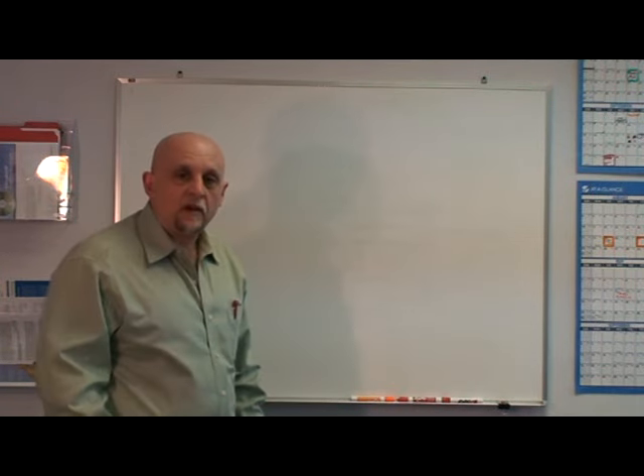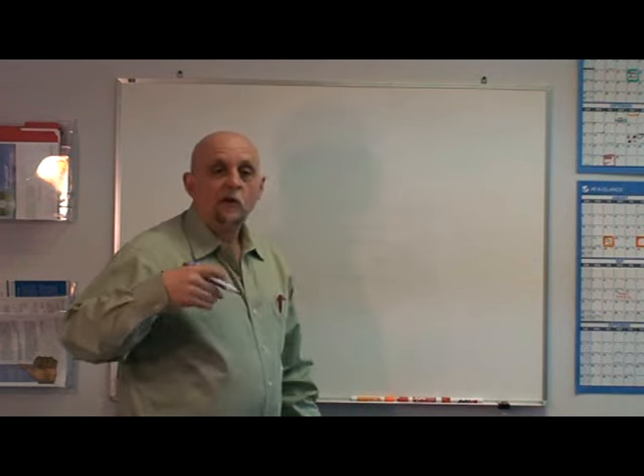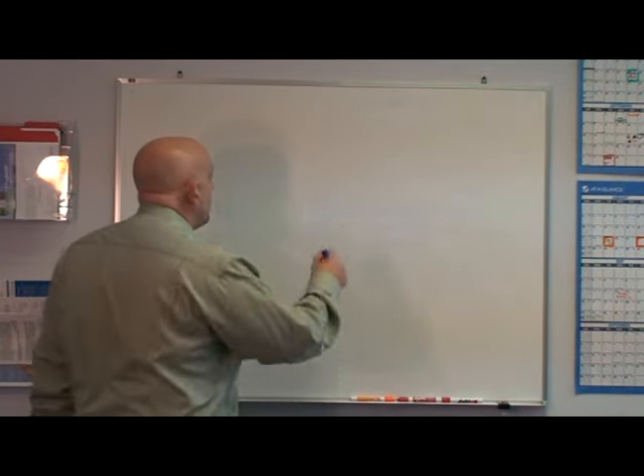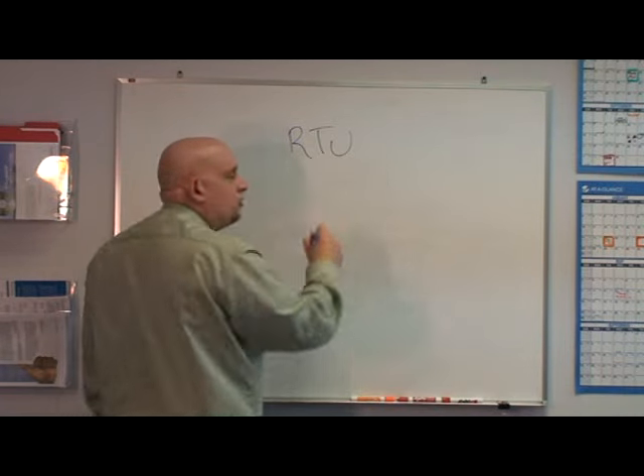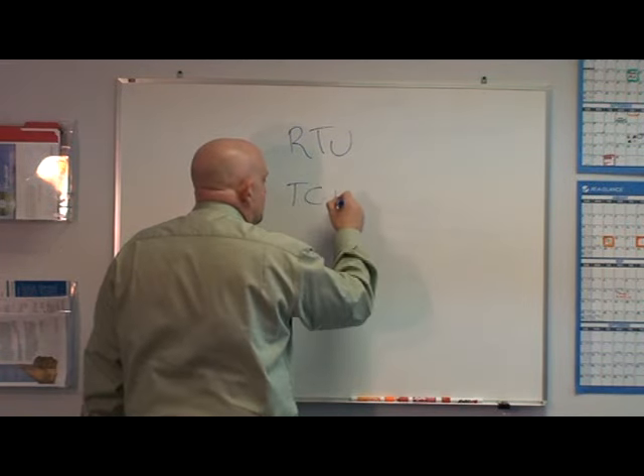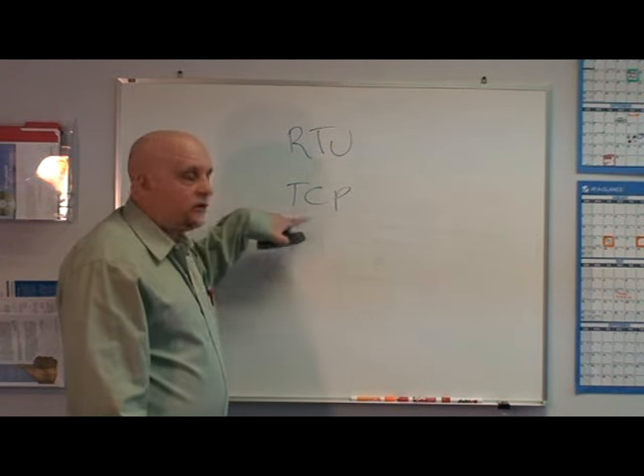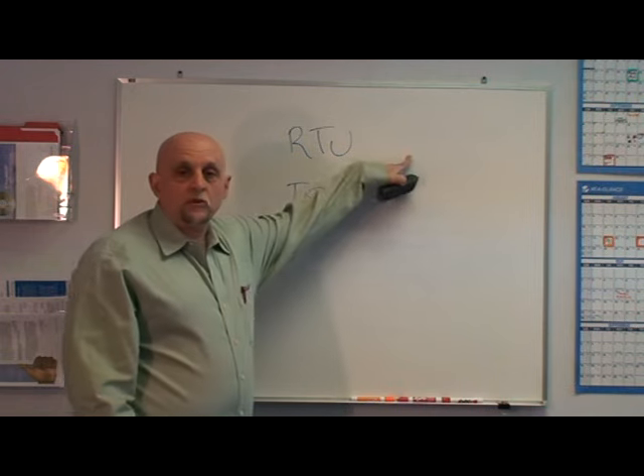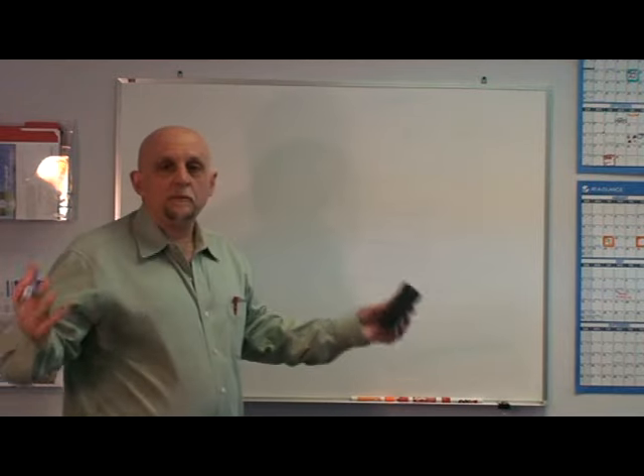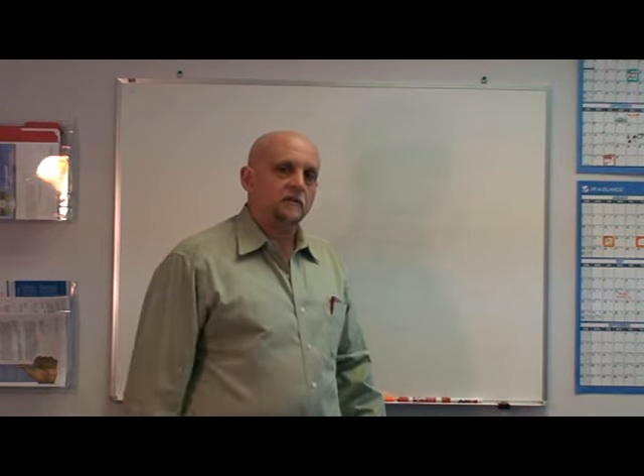So Modbus RTU is an RS-485 protocol. A lot of people ask me, can I do Modbus RTU in RS-232? Well, yeah, you can if you just have two nodes. Then you're fine. Now, Modbus RTU, what does the RTU mean? RTU means remote terminal unit. Does that mean anything to us? Well, not really. It just distinguishes it between the TCP version of Modbus. Same packet, same data, same everything, only this goes in an Ethernet packet. This just goes out as serial bits on RS-485.